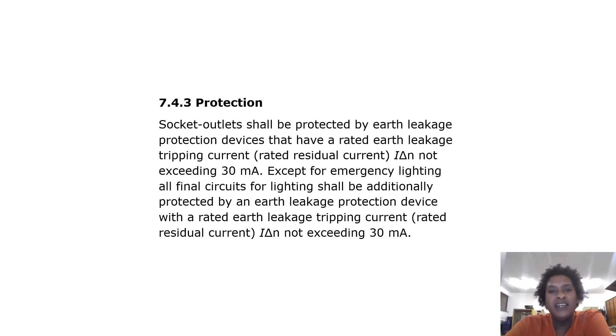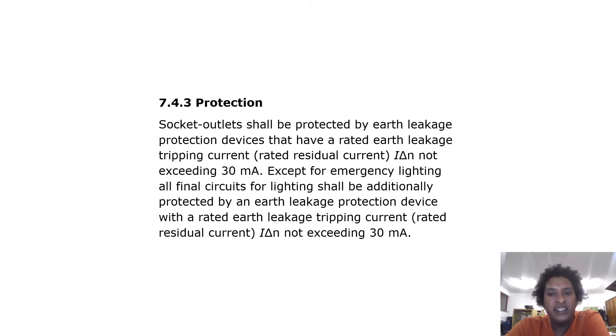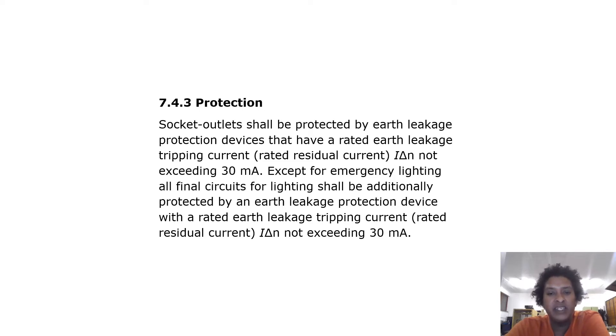Protection. Socket outlets shall be protected by earth leakage protection devices that have a rated earth leakage tripping current not exceeding 30 milliamps. Except for emergency lighting, all final circuits for lighting shall be additionally protected by an earth leakage protection device with a rated earth leakage tripping current not exceeding 30 milliamps.